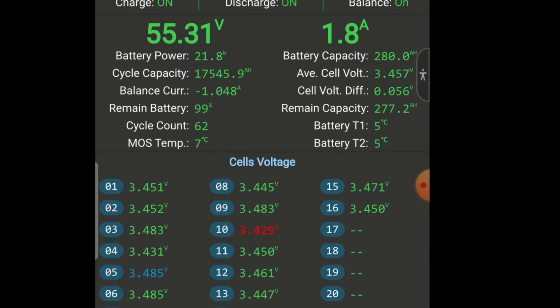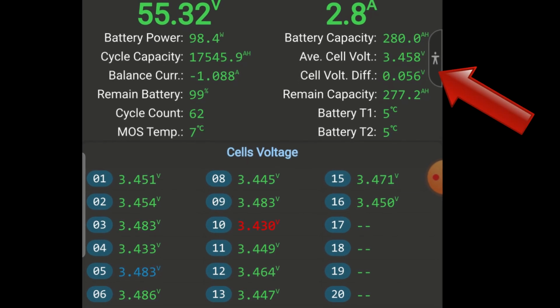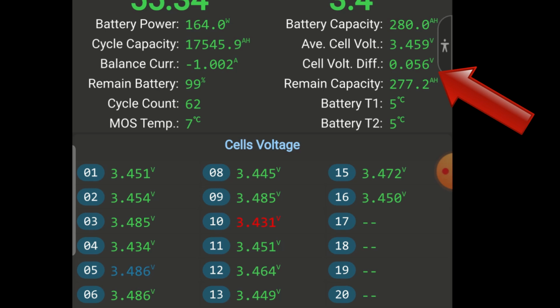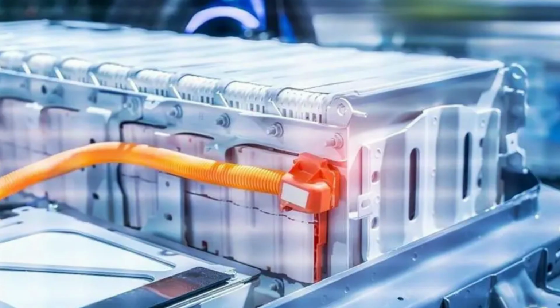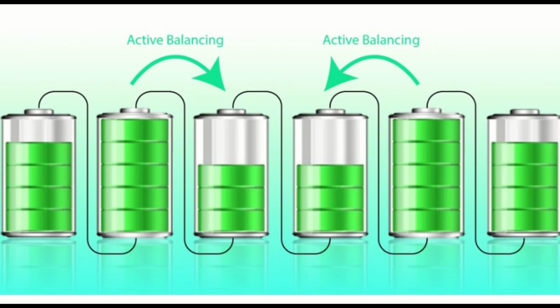After a certain number of cycles, we can see a deviation in voltage between cells. Because of this, you can no longer use the full potential of the battery, and it can have an impact on the lifetime of the cells. Preventive maintenance tackles this issue before it gets out of hand. And yes, the BMS has a built-in balancer, but I'll explain later why this can't always keep up with your system.